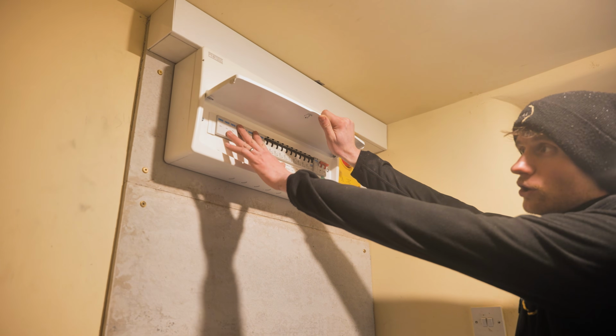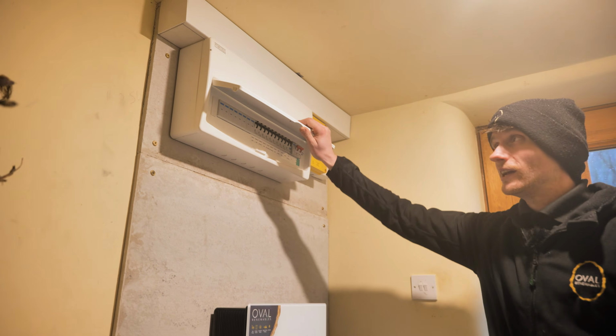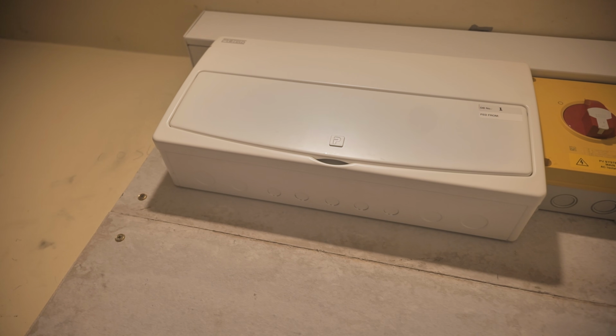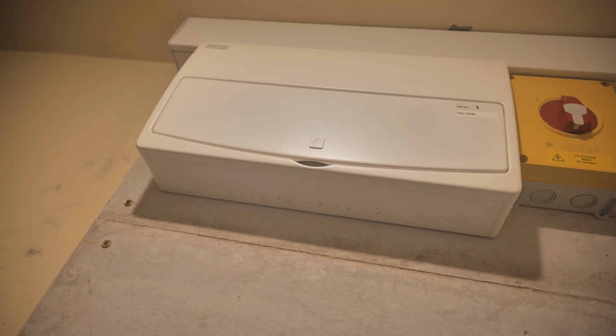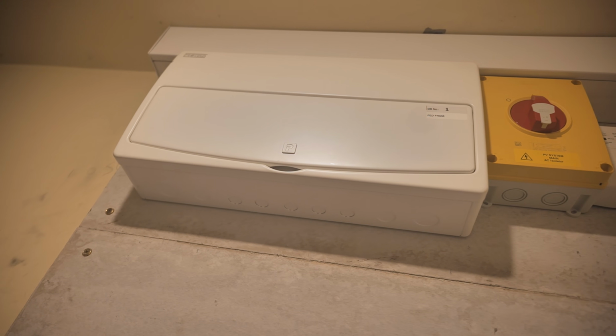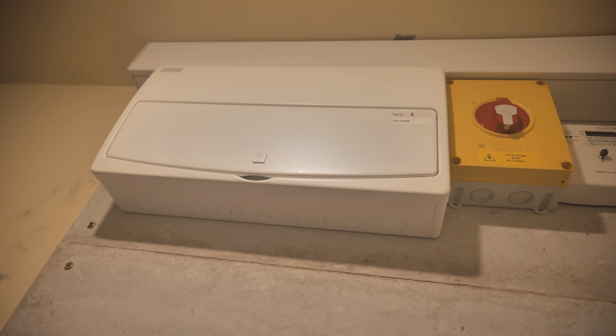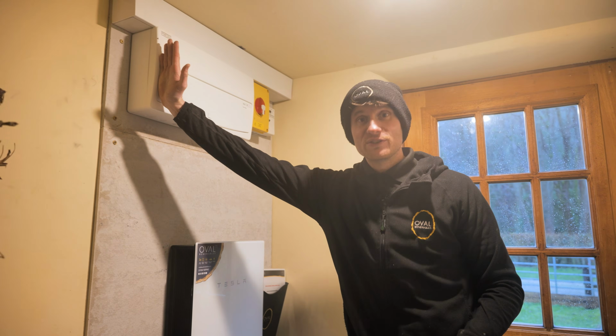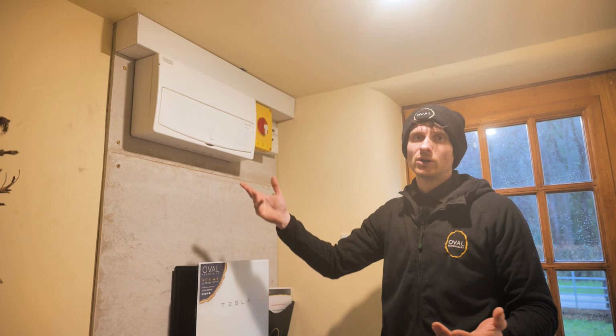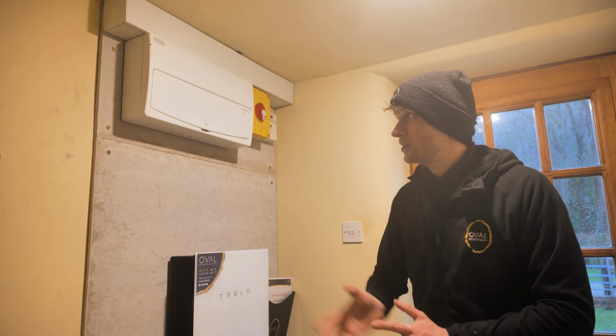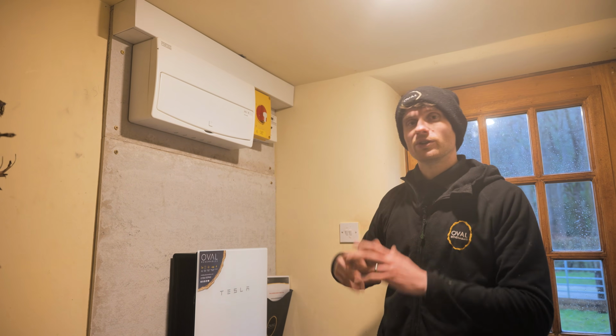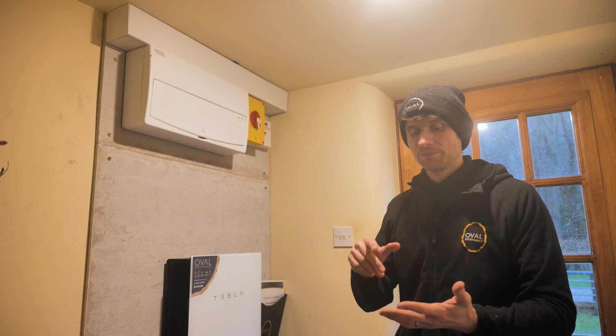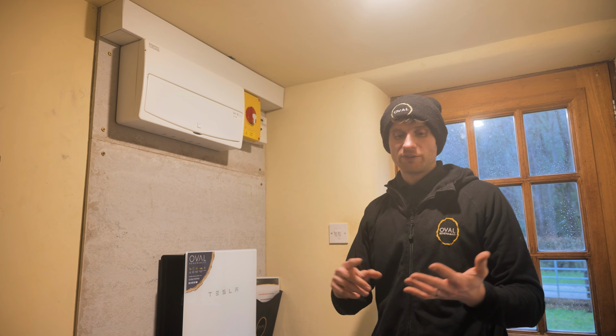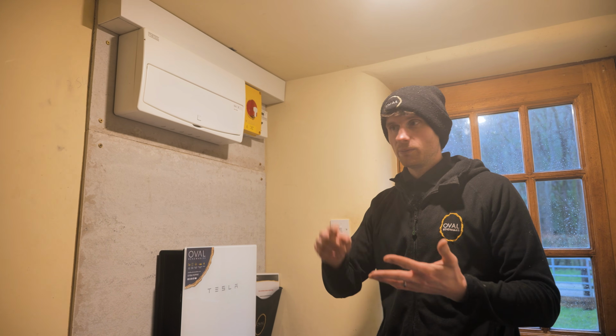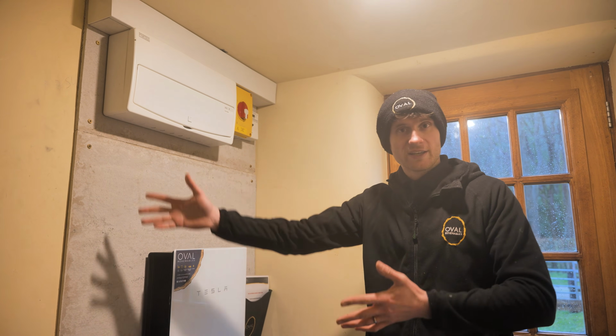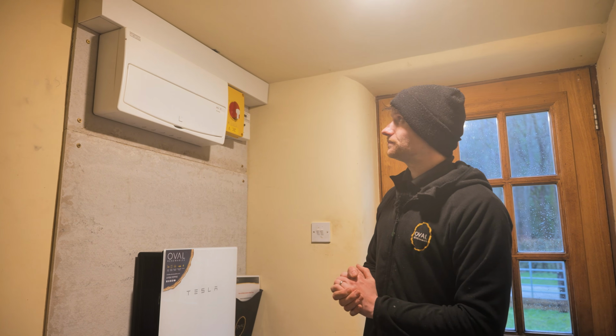This property is going to have an extension, and putting in a larger distribution board costs almost nothing extra, because we've still got to install a board either way — the difference might only be around £20. So we've installed a nice large distribution board to give this property flexibility for potentially an EV charger in future, an air source heat pump, or more circuits for the extension. We've got that spare capacity.